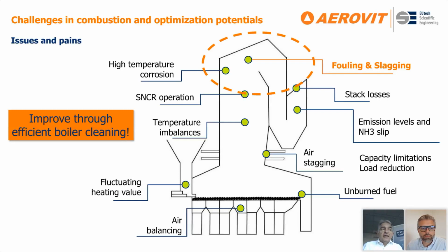You face imbalanced temperatures, hotspots close to the walls, high CO concentrations causing high-temperature corrosion, and temperatures exceeding the ash melting point, which results in sooting and fouling of your heat exchangers. With this, you face a drop in heat transfer efficiency and overall efficiency, and it also endangers your process, because the soot or deposits on the surfaces might damage your furnace.